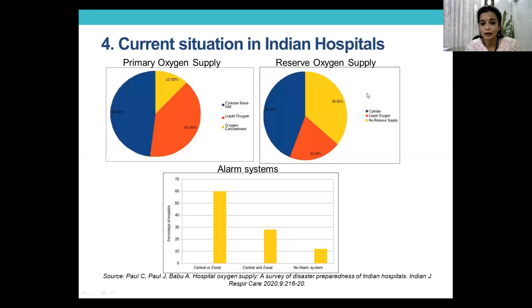Now, while you're planning systems, these are some of the good practices that you'll have to remember. Certainly auto changeover from supply to backup. You cannot depend on your technicians to say, I'm looking at it every minute. A common mistake that people make is to put a single pipeline from the primary source to save cost. You need to have 2 or 3 pipelines going, so there is no difficulty when one fails.